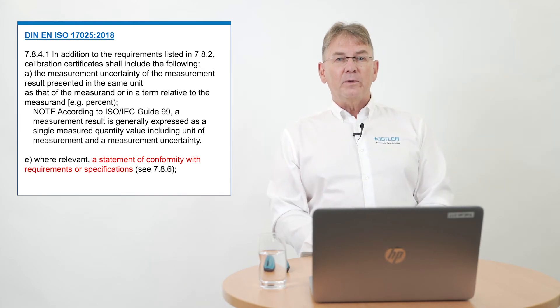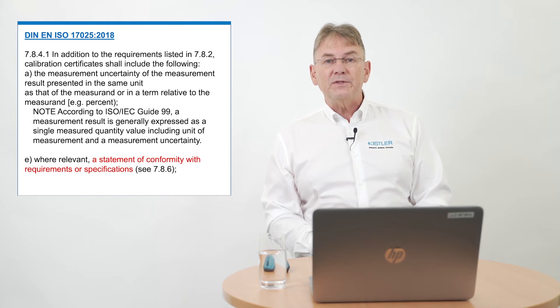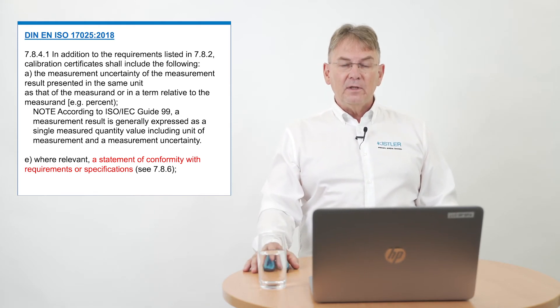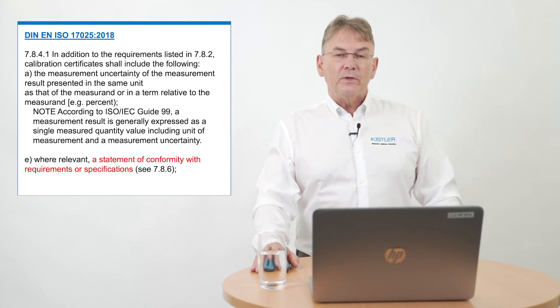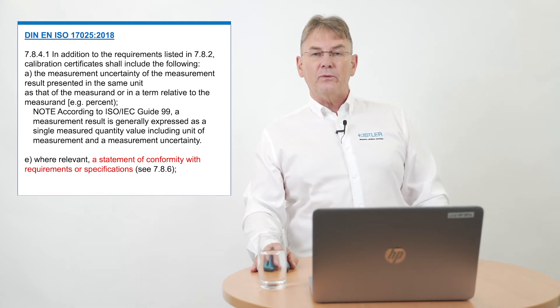Something new in this norm is point E, which says: where relevant, a statement of conformity with requirements or specification. Where relevant — who determines what is relevant? That's you, the customer. If you want a statement of conformity, you can insist on it; it becomes relevant for the laboratory and they have to include it. In the simplest case, it's nothing more than a sentence saying 'this device is compliant to the manufacturer's specifications,' or very short: it passed or it did not pass.